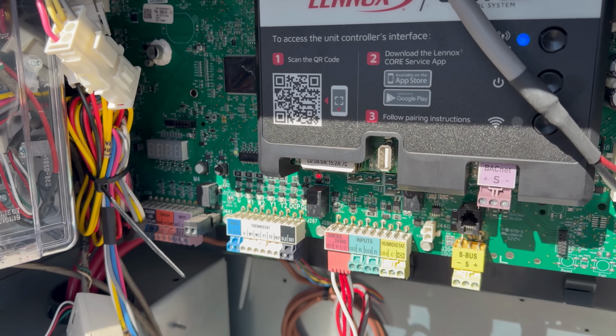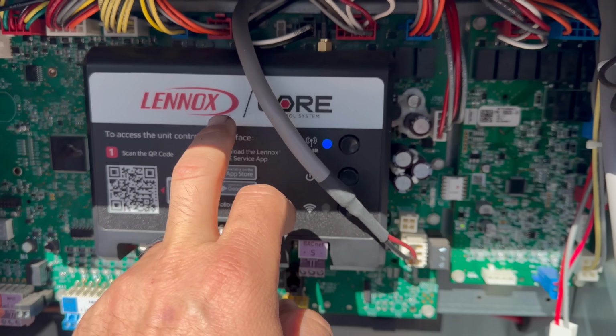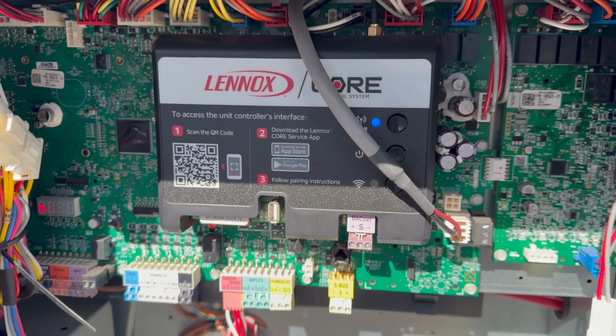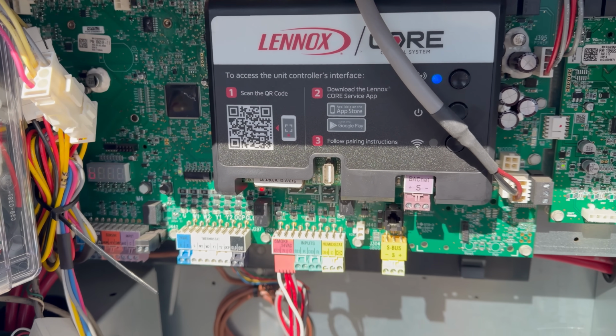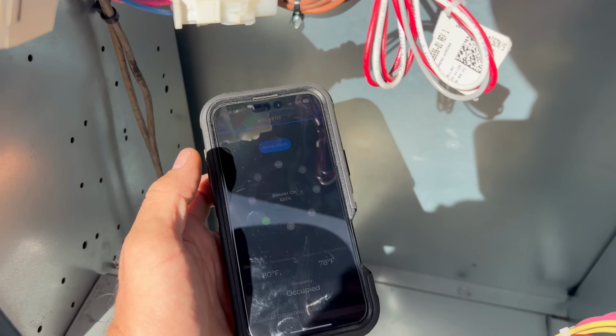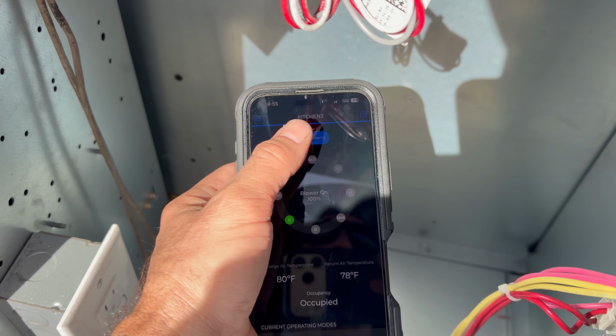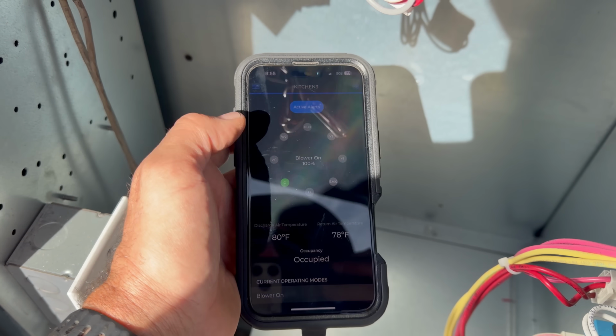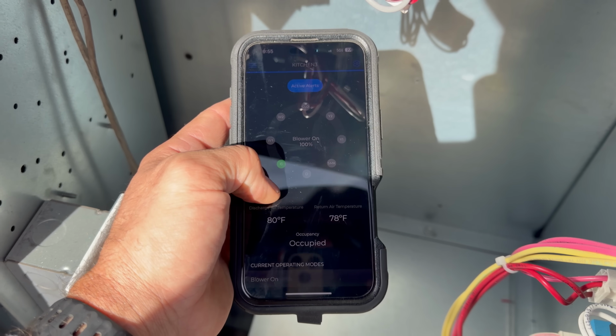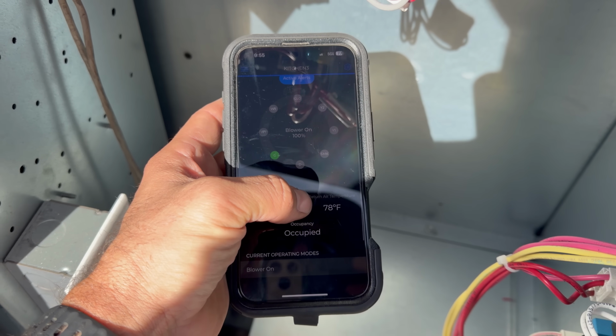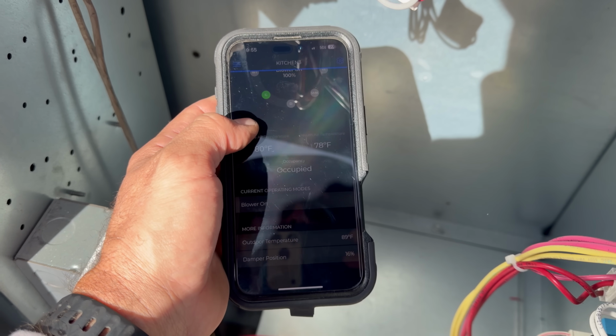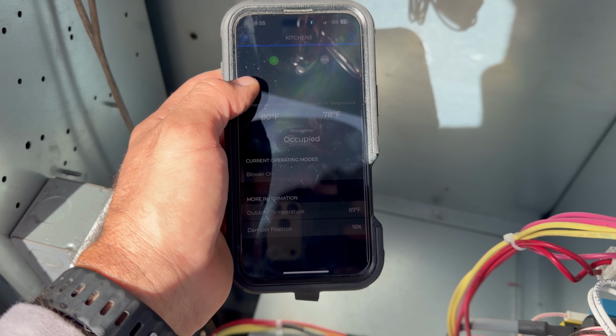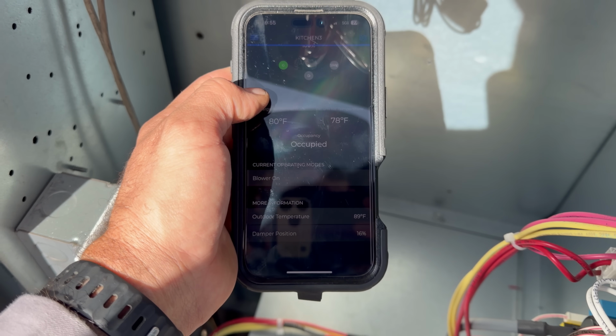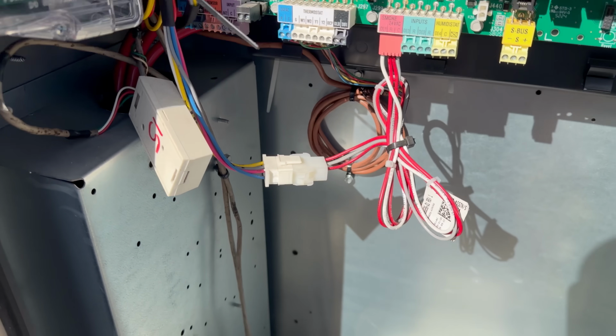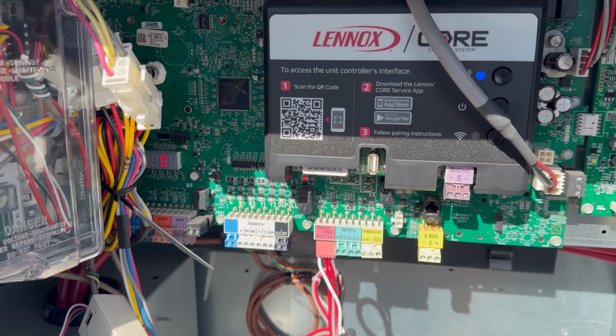Can I see your phone real quick? Will you open it up? We connected to the Core app and we looked to see if there was any error messages. So if we look right here, we're in the Core app right now. If we go to active alerts, we have none, no active alarms, okay? So basically we only have a call for G. It's 78-degree return air, 80-degree discharge air, blowers on, damper positions at 16%, outdoor temperatures 90 degrees. It's already 90 degrees. So why is it that we don't have a call for cooling?